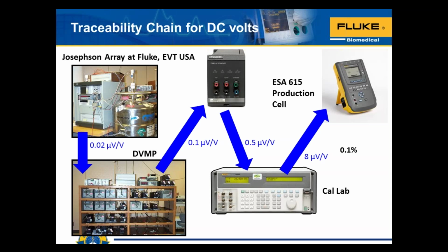And one final step, whether it's to your DMM or to the electrical safety analyzer that you get from Fluke Biomedical, that uncertainty has now become 8 microvolts per volt. That is our uncertainty. But you see, it is way, way, way certain. It's a very, very accurate measurement compared to what you're going to expect your measurements to be. So we see a 0.1% uncertainty of the measurements that we're making with the electrical safety analyzer that we put into your hands.